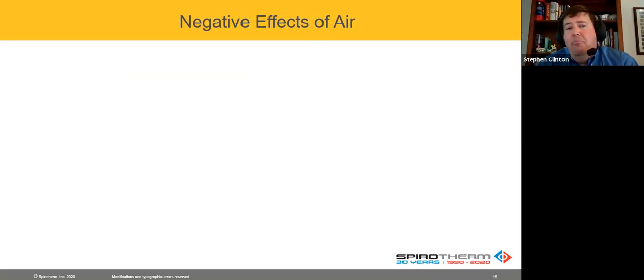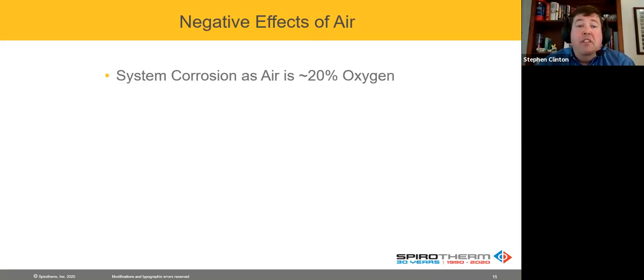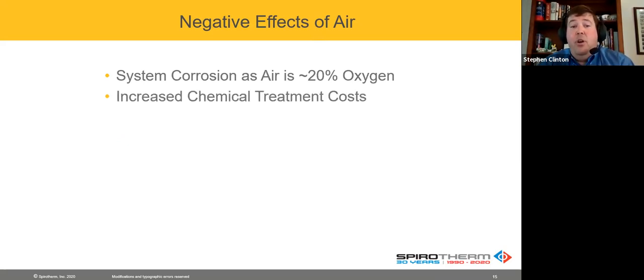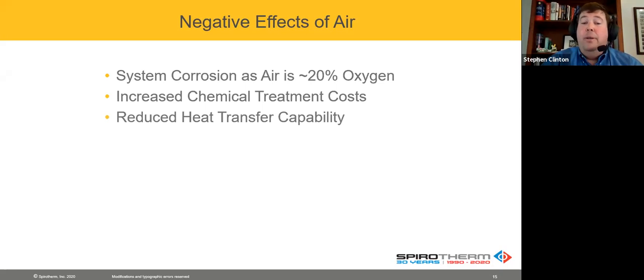All right, we're going to talk about, so what if we have air in the system? What difference does it make? Well, the first part we've already talked about, we've shown you some examples that systems corrode. Air is 20% oxygen. And so if we do that, how do we combat that? Oftentimes it's chemical treatment. Sometimes it's not, but proper chemical treatment can help the rust, but it cannot address the issues with heat transfer because, as we've already talked about, that air is an insulator. It's affecting the ability of that fluid to transfer heat.